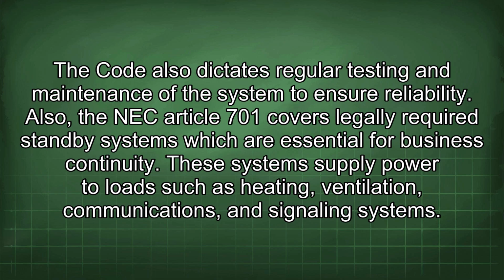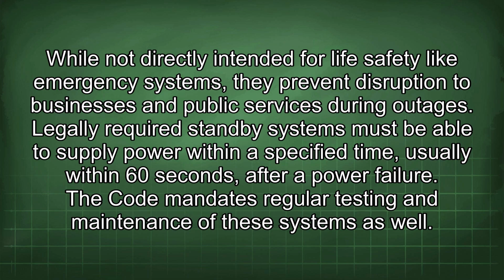Also, the NEC Article 701 covers legally required standby systems which are essential for business continuity. These systems supply power to loads such as heating, ventilation, communications, and signaling systems. While not directly intended for life safety like emergency systems, they prevent disruption to businesses and public services during outages. Legally required standby systems must be able to supply power within a specified time, usually within 60 seconds after a power failure. The code mandates regular testing and maintenance of these systems as well.